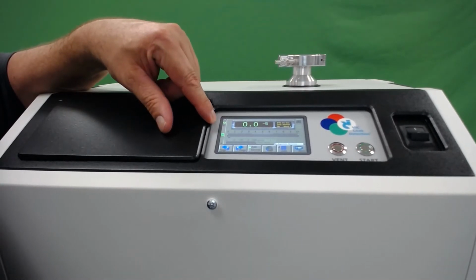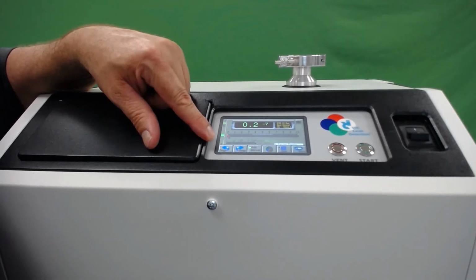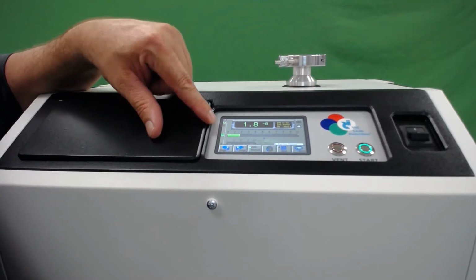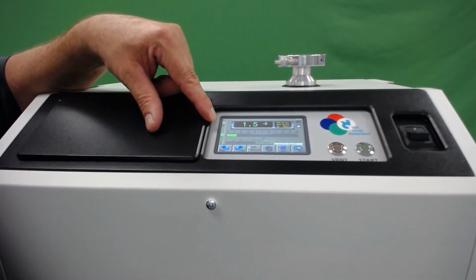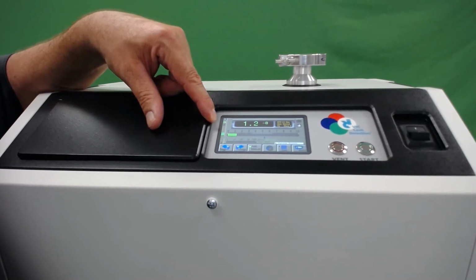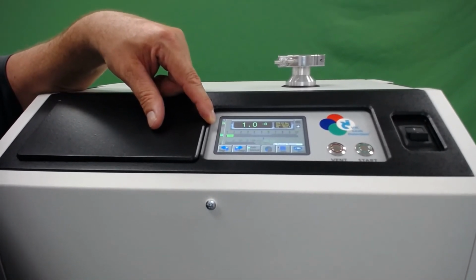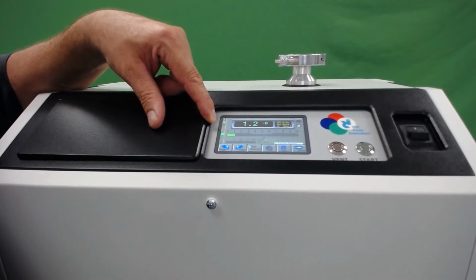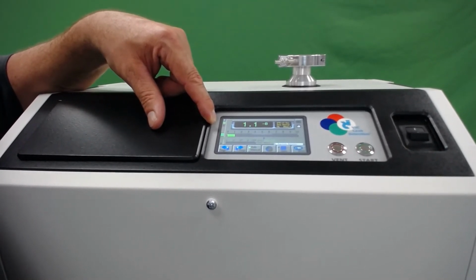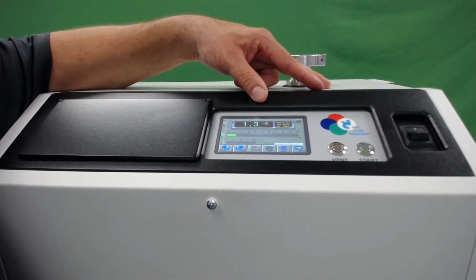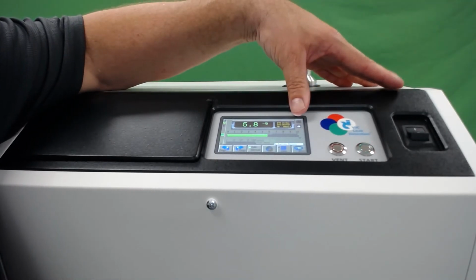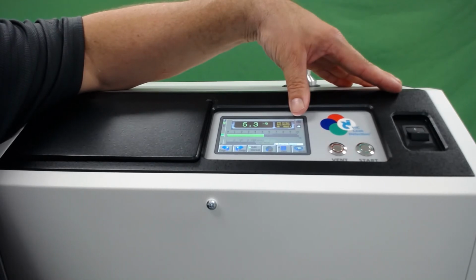Once the machine enters reverse test, the test port will continue pumping down, and when the pressure achieves the required level, the machine will transition from reverse to direct testing, and the letter D will be indicated in the upper left-hand corner. Once we go into direct testing, the machine will have capability to test in the 10 to the minus 9 and 10 to the minus 10 leak rate ranges. Indicated on the side is an arrow based on a programmable set point indicating accept or fail.